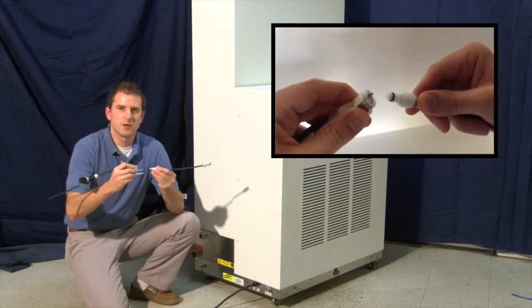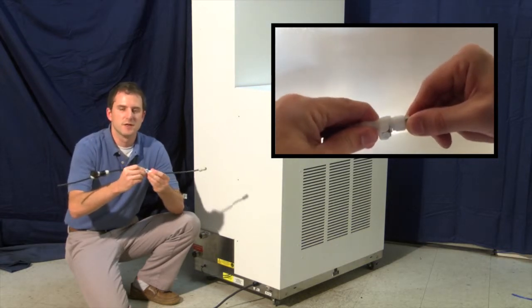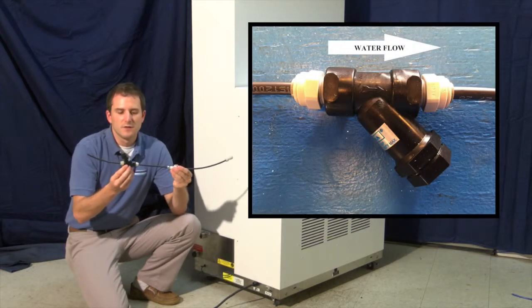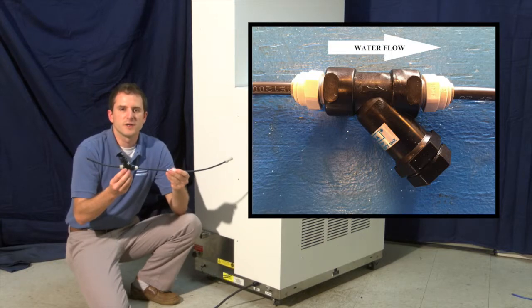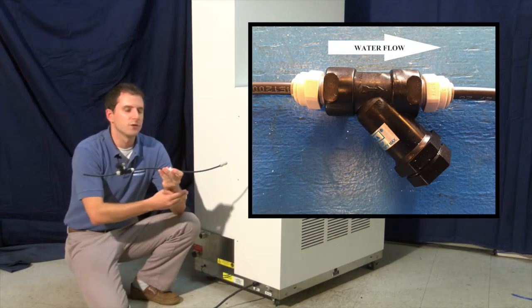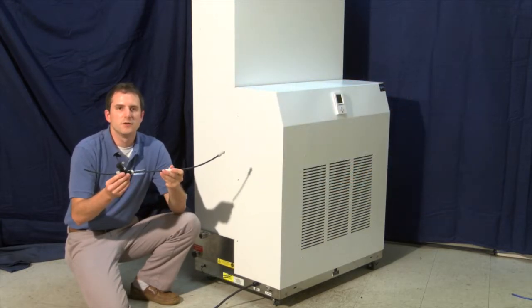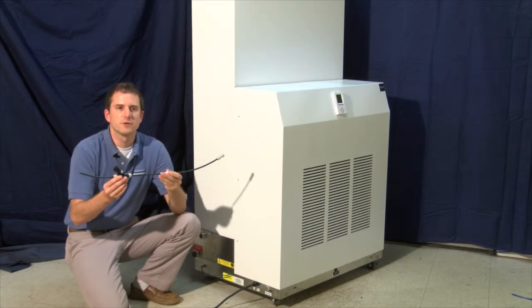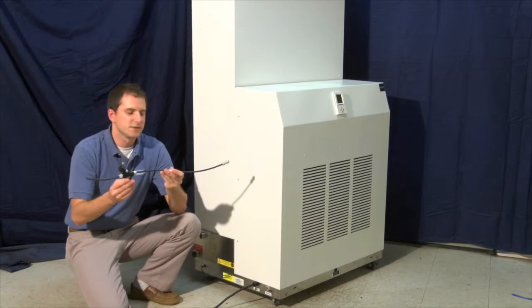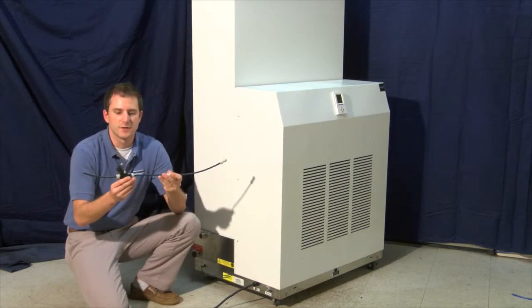Note, water will not flow unless the male and female are connected, and most importantly, the debris Y strainer. This strainer will remove debris in the water line and keep it from entering your humidifier. Note, humidifier overflows are mostly caused by debris in the water line sticking in the humidifier solenoid.